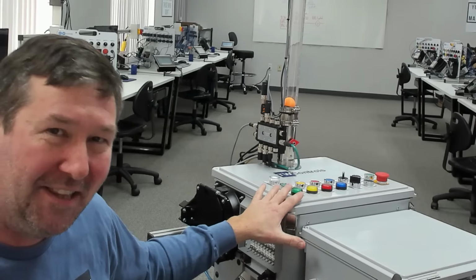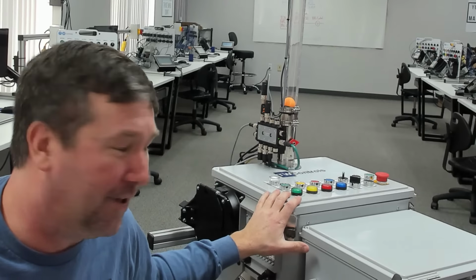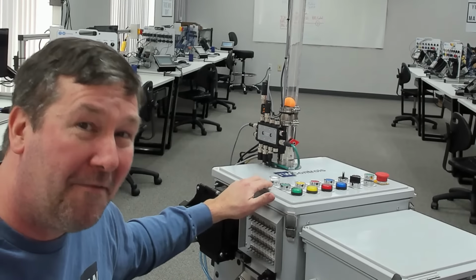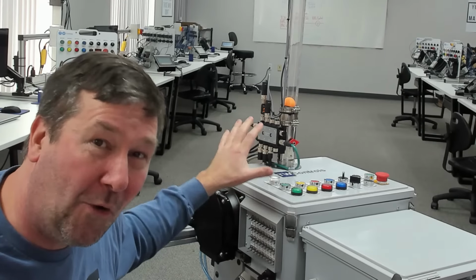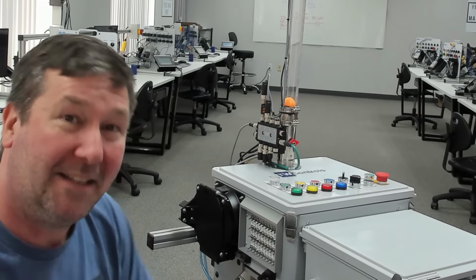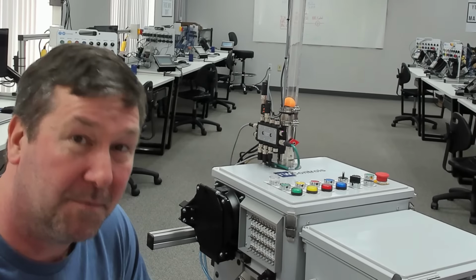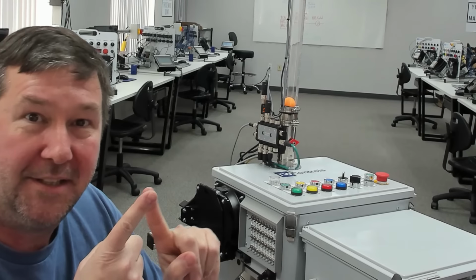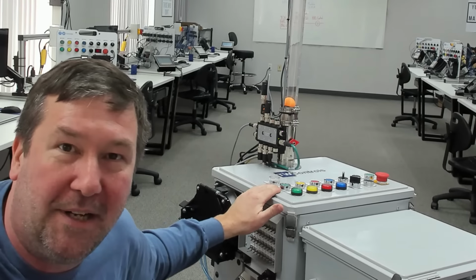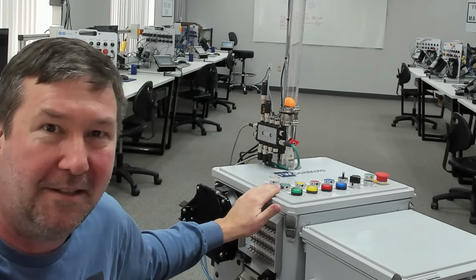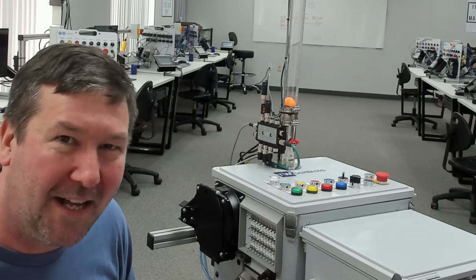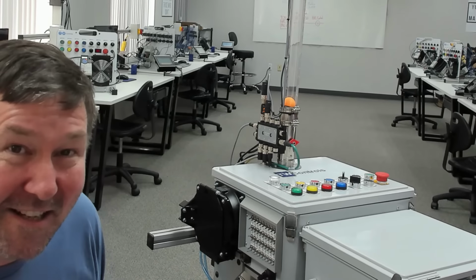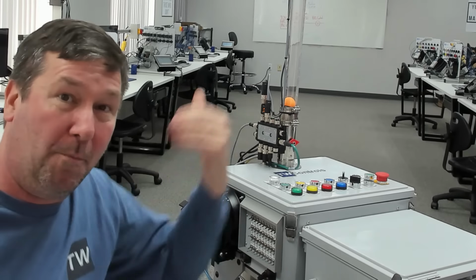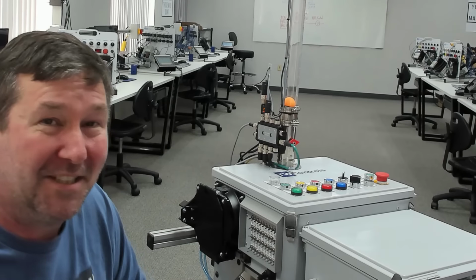Even on a machine this small, because I counted it up this morning, if you go off of inputs, there's 46 possibilities that could be preventing this machine from starting. The issue is, if we check the green button and it works, have we learned anything about the other 45 conditions? Have we narrowed anything down, or did we just figure out one and we're back at square one? Yeah, we're back at square one.